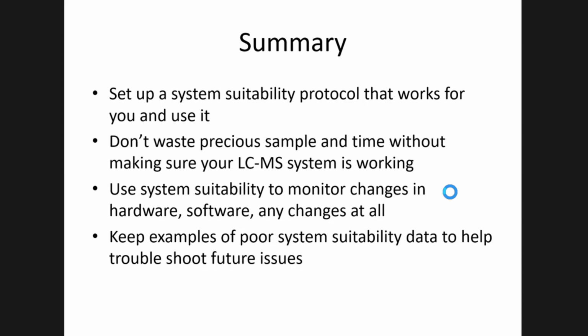So AutoQC has a series that it automatically looks for. If you're not using that, these are the ones that I would keep track of, because things like peak shape and full width half max can be related to your column and LC and the connections. If all of a sudden you're seeing carryover when you shouldn't normally, that's another thing that would be more LC indicative.